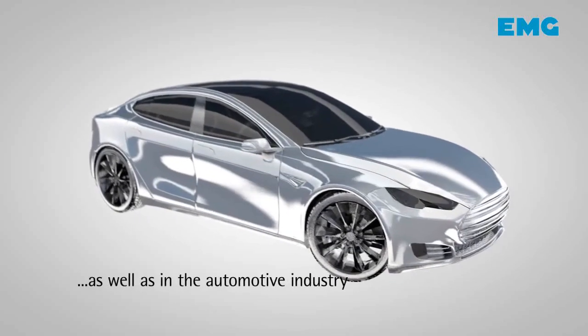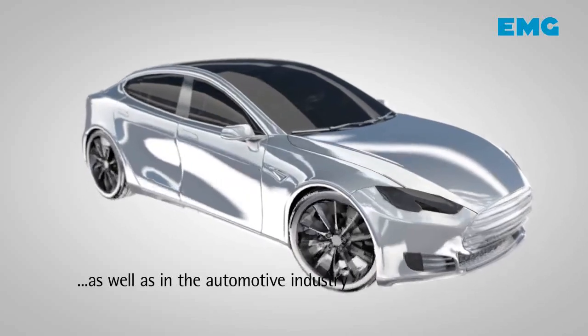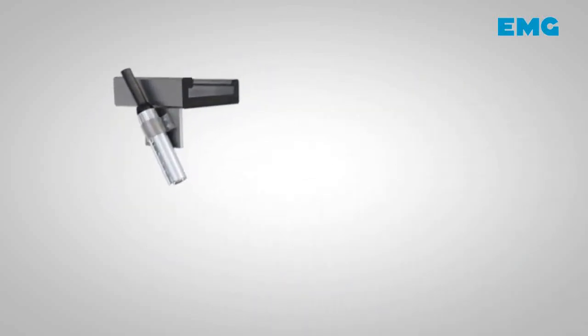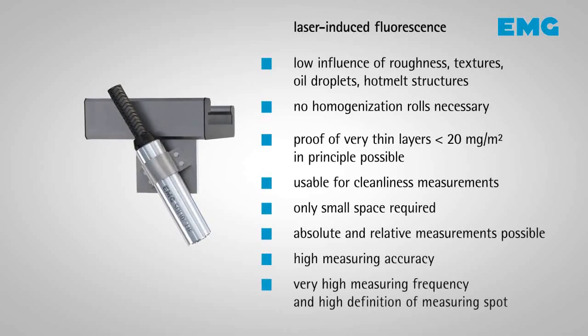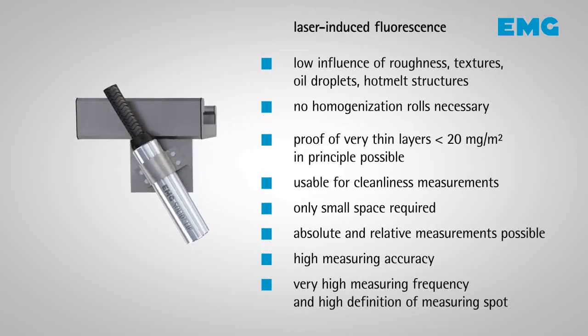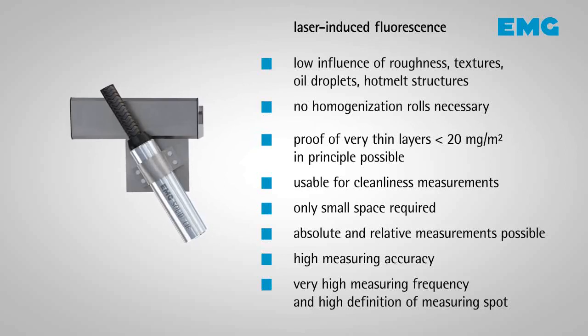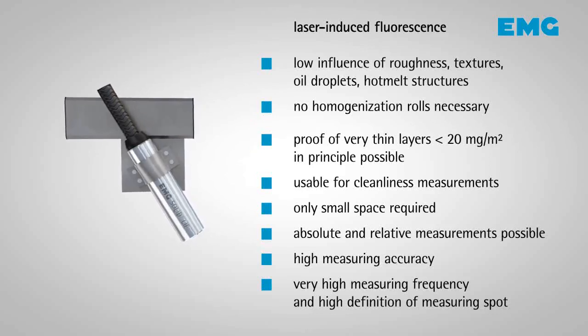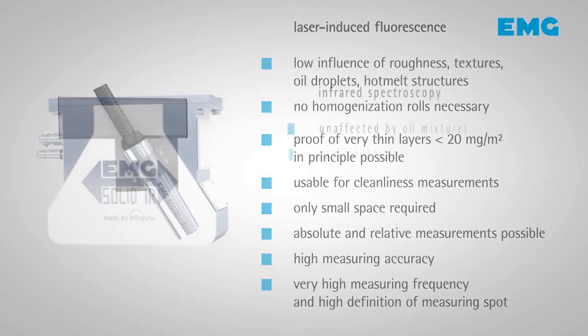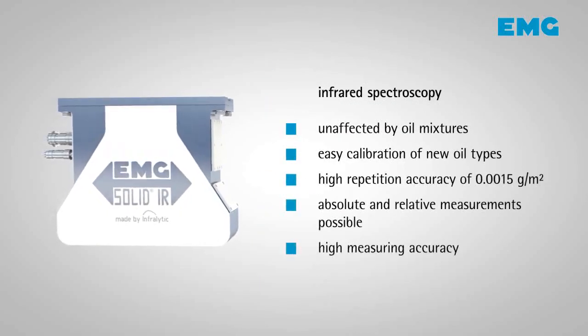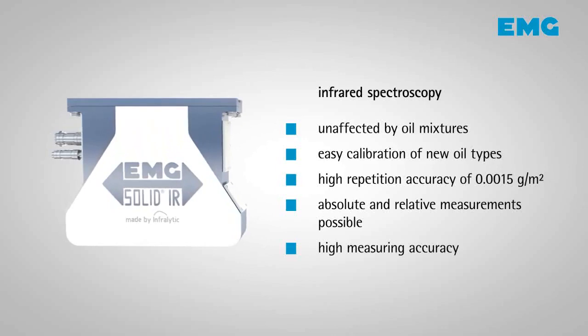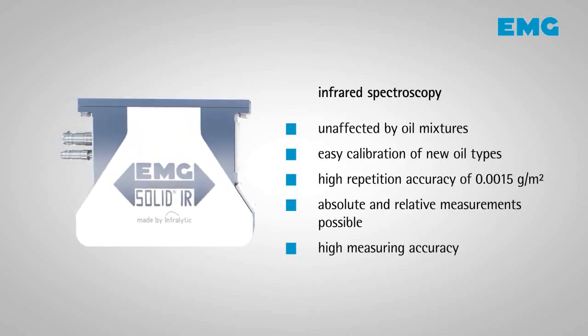The laser-induced fluorescence measurement requires only limited installation space, is not much influenced by surface textures, oil droplets or hot melt structures, and has a very high sensitivity. The infrared technology on the other hand is not affected by oil mixtures, is very robust and applied in a lot of industrial applications, and it also has a very high measuring accuracy.